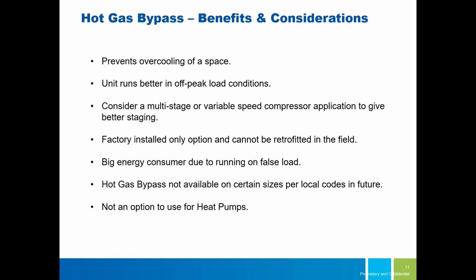It may be able to be done, but that's just not something I'm aware of, and someone can correct me if I'm wrong. Now, one of the other drawbacks of this is that it's a huge energy consumer, right? If you're running your 10-ton unit like it's a 10-ton unit all the time, guess what happens when the power bill comes? It's not going to be low. So that's something you want to consider.